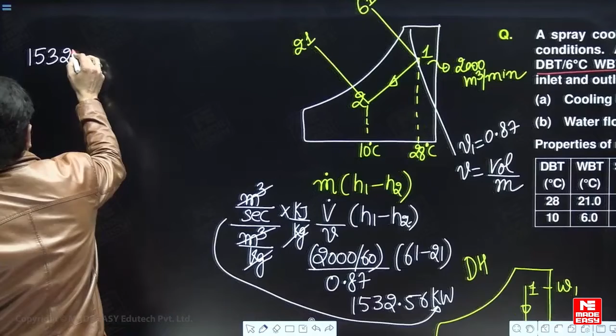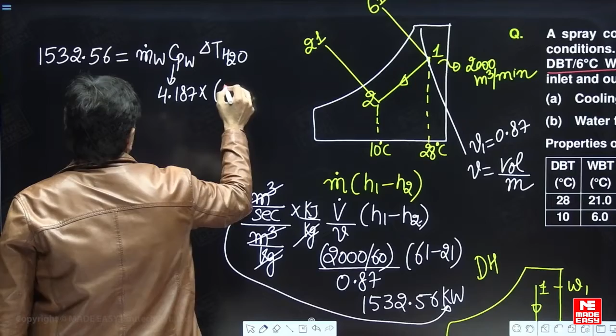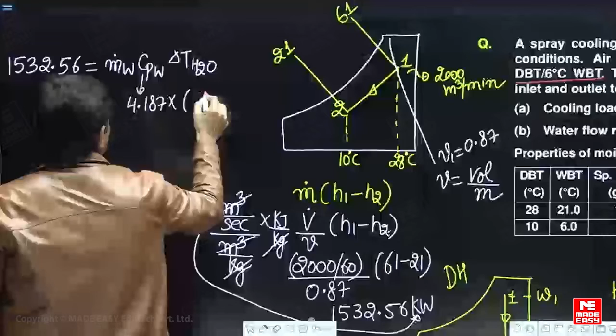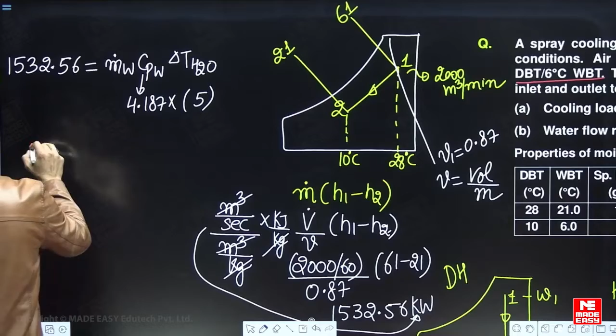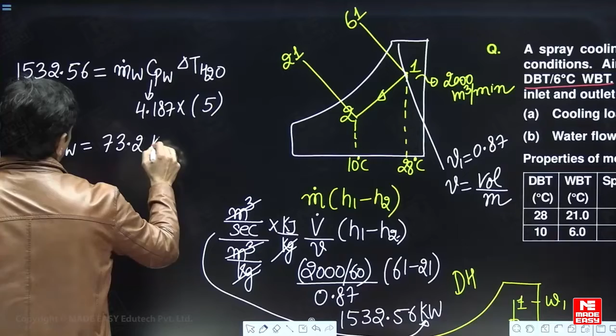So mass flow rate of water equals Cp of water into delta T across water. What is the value of Cp of water? 4.187, and this is increased by 5, that is 12 minus 7, equal to 5. So divided by 4.187 and 1532.56 divided by 4.187 divided by 5. This will come out as 73.2 kg per second. So this is the mass flow rate of the water.